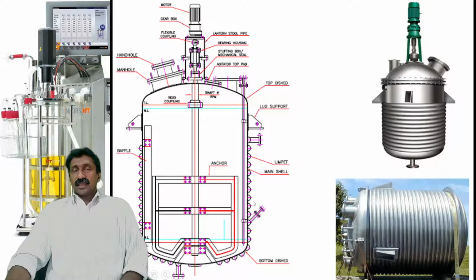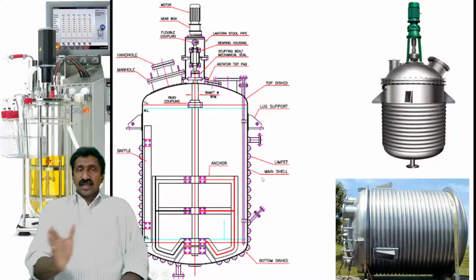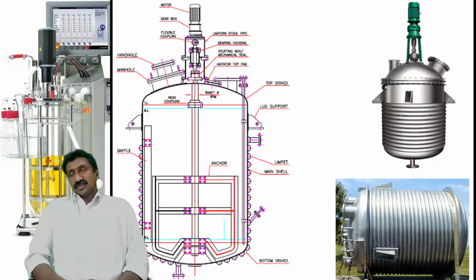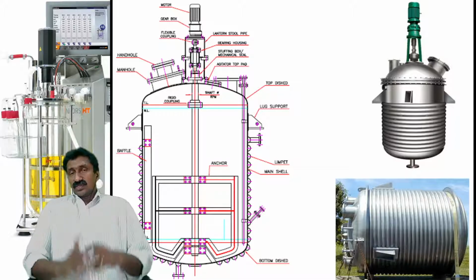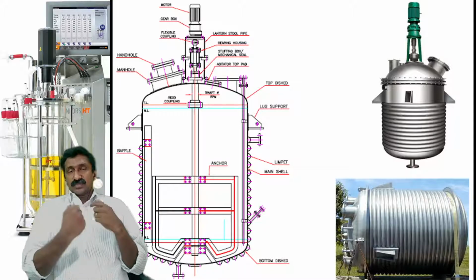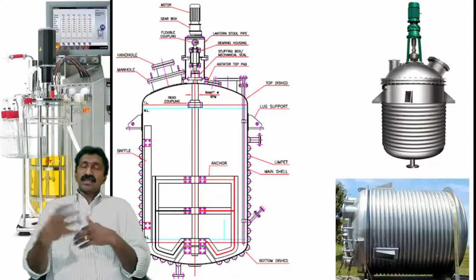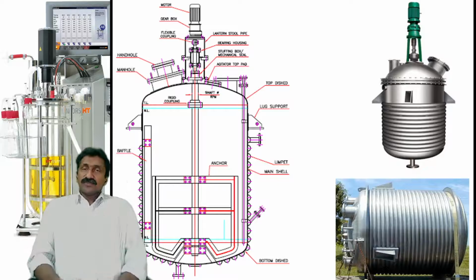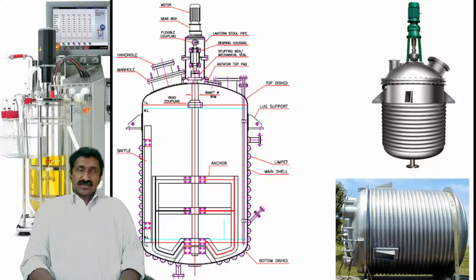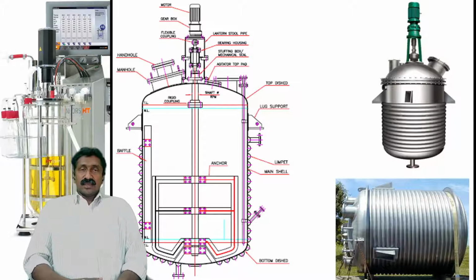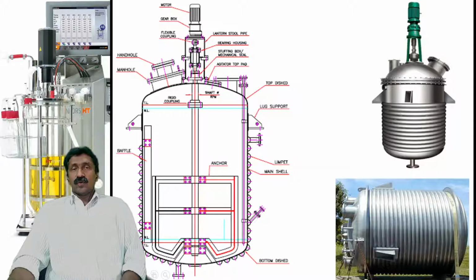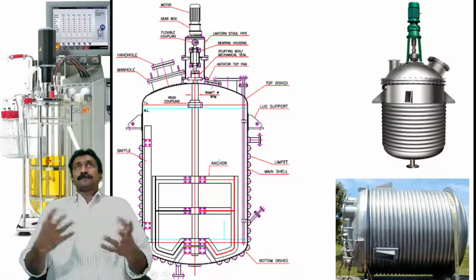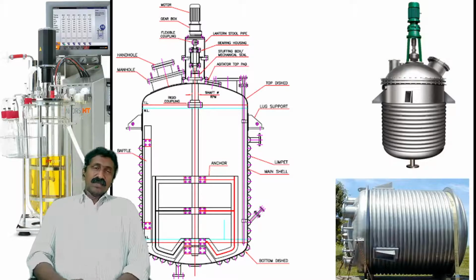So this design ensures a better heat transfer through that flat surface which is continuously in contact with the vessel wall. And also, since you are providing a pipe system, turbulent flow of the fluid can be ensured. Instead of just filling the coolant within the space of the jacket and keeping it static for some time, a more turbulent or forceful flow of the coolant can be passed through these pipes so that better heat transfer efficiency can be achieved.